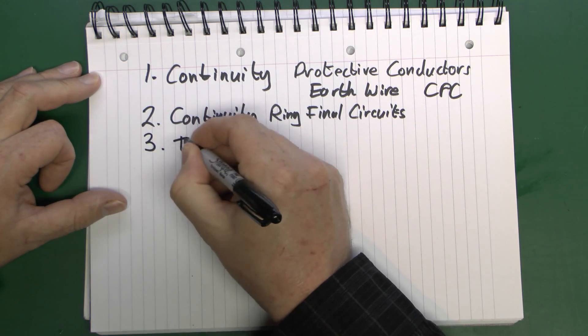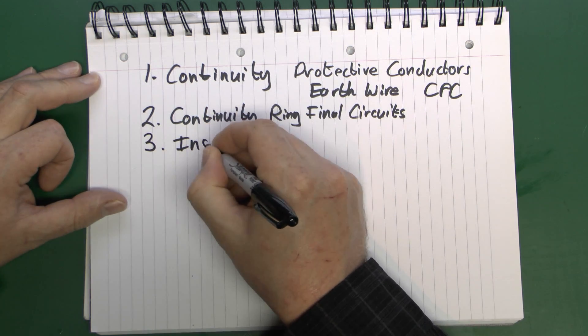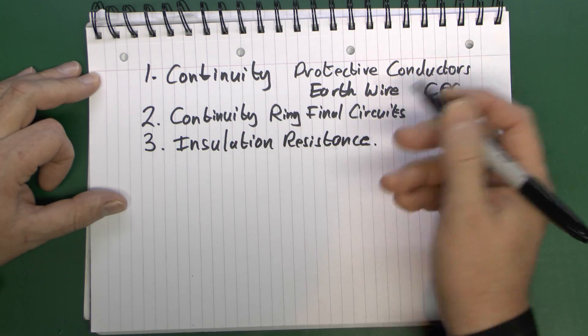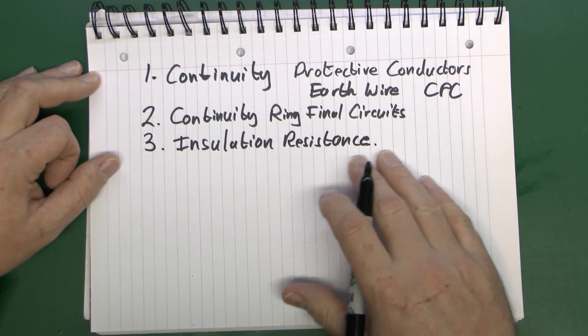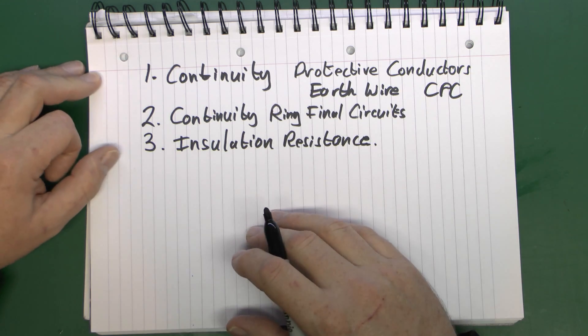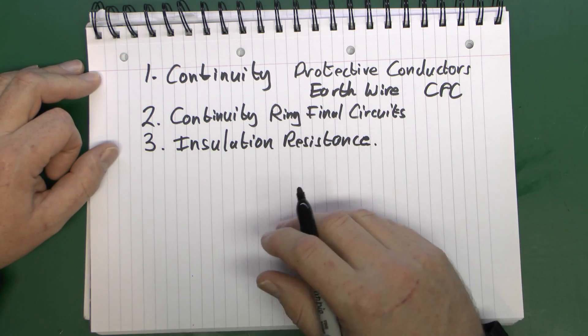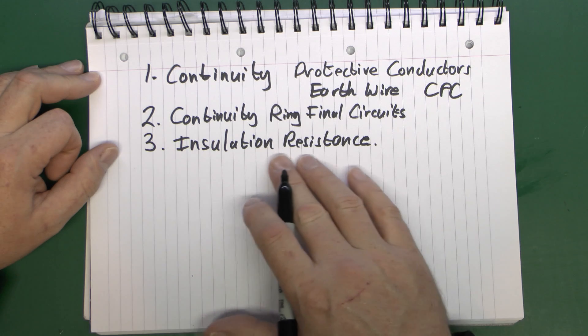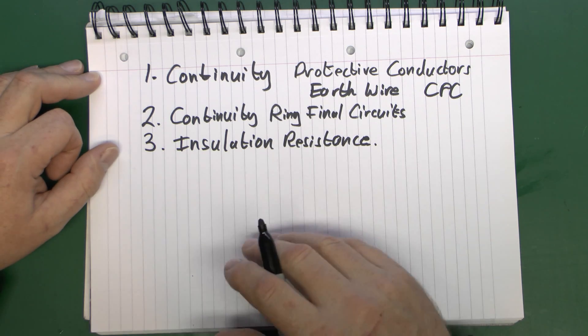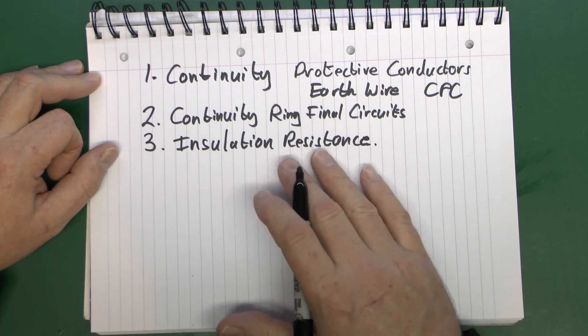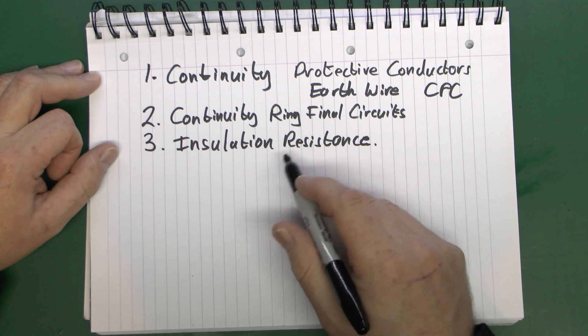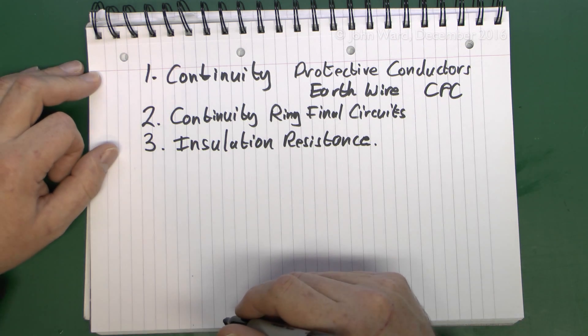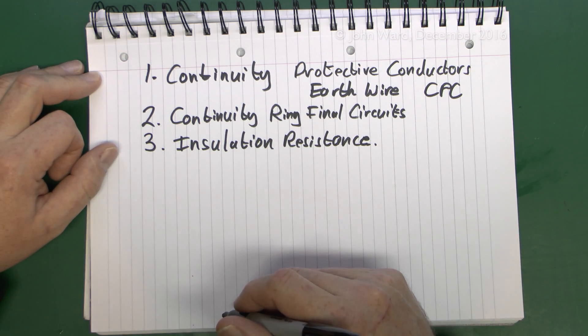Test number three is insulation resistance. This is the one where you typically apply voltage — say 500 volts from a test device — and check between line, earth and neutral. You're looking at the quality of the installation, making sure the cables haven't been damaged or there's no defect anywhere. This is done on all of the circuits, regardless of what type they are.